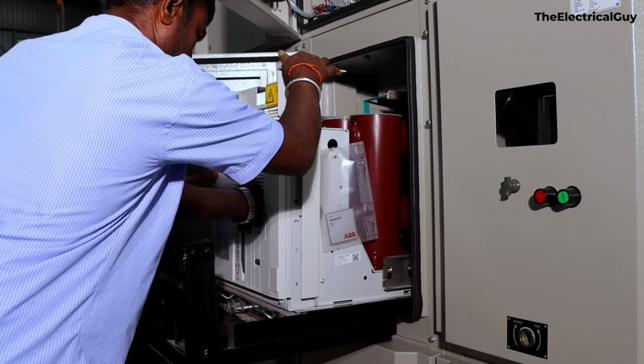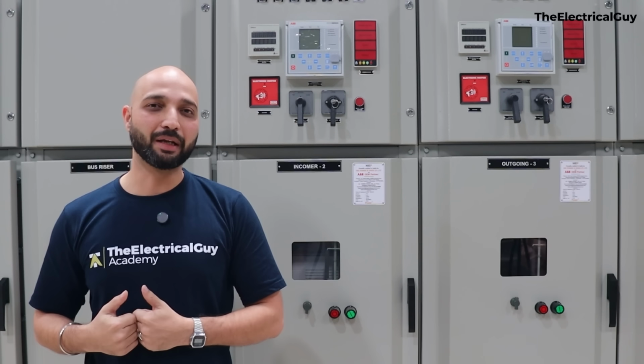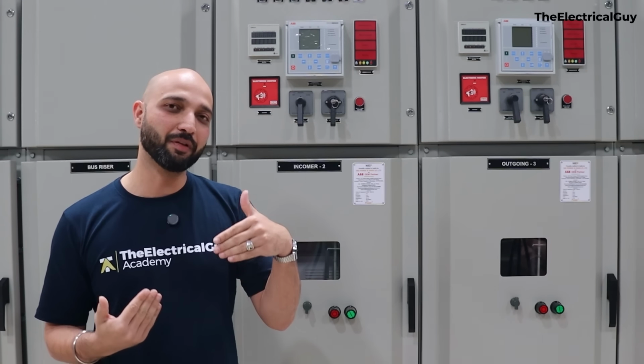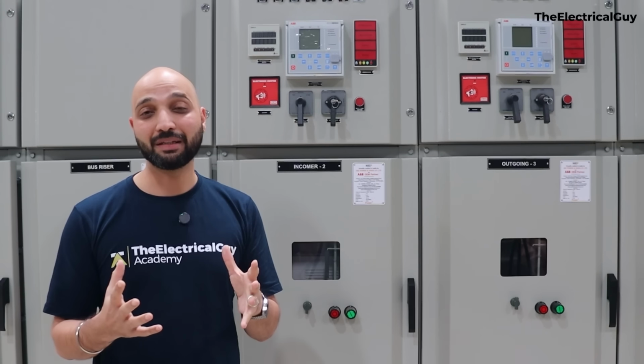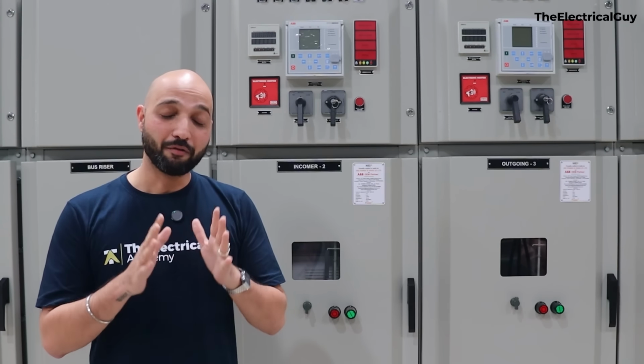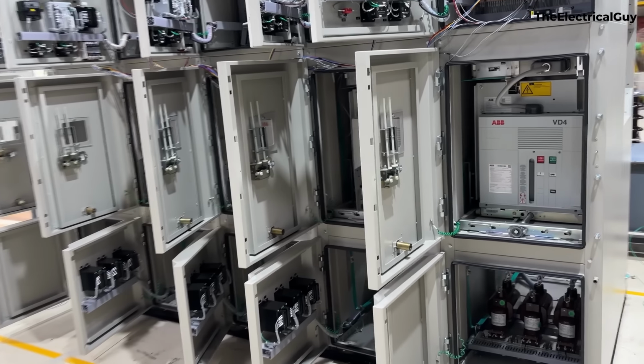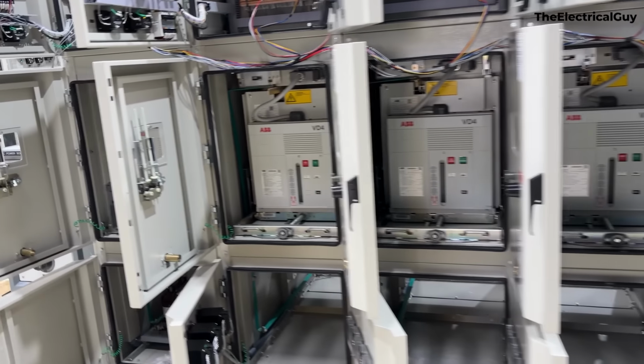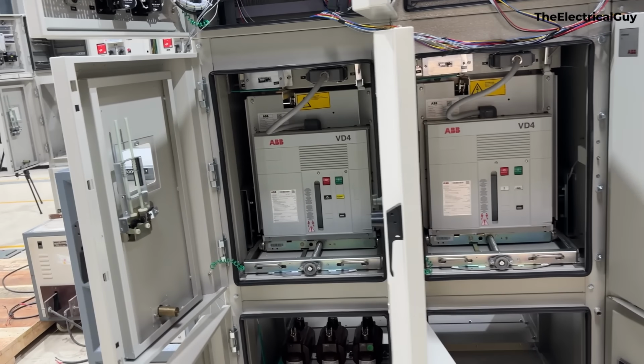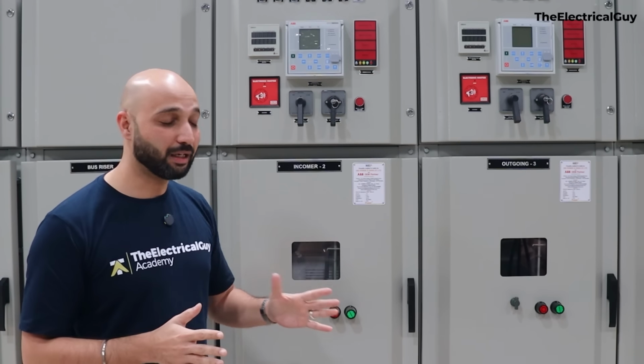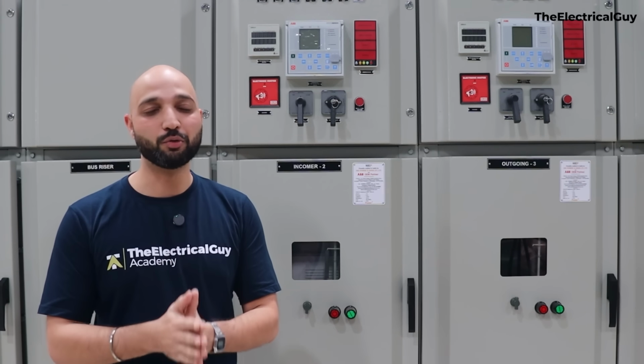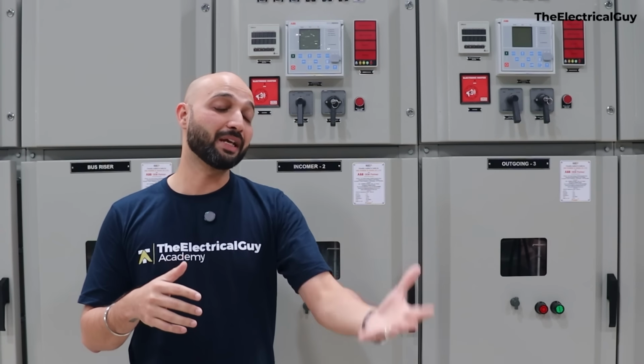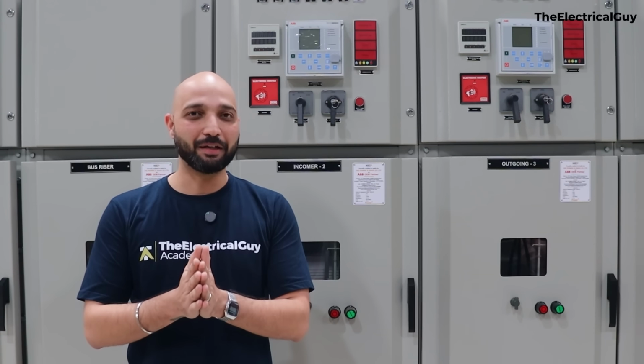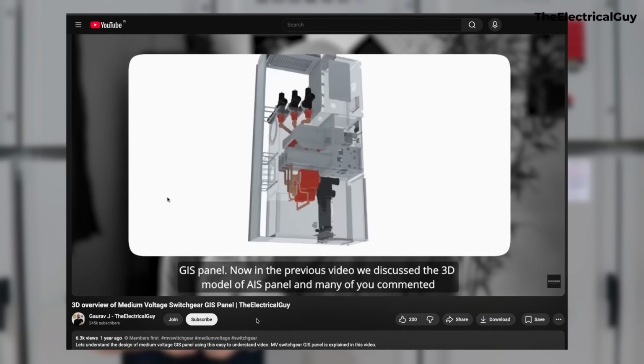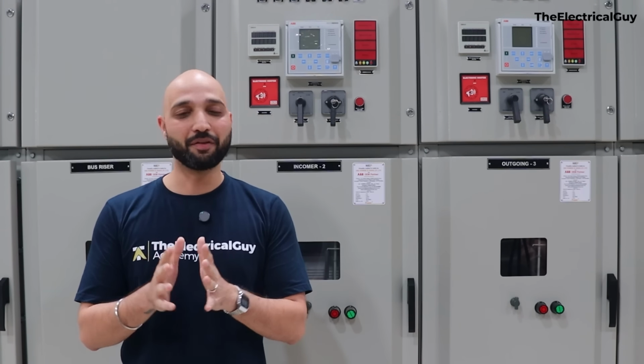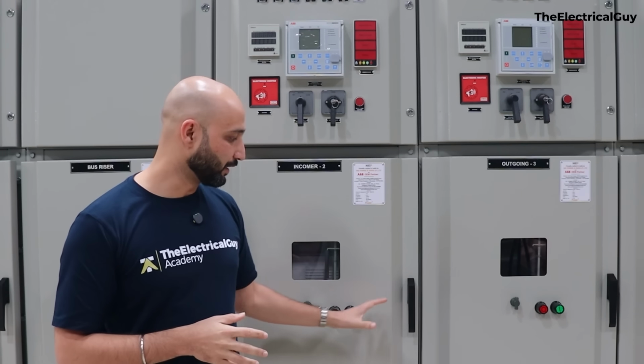Now the advantage with this, we already talked about. When you remove this breaker, we also get an isolating distance between the two live wires. That basically serves as an isolator. So when we use this withdrawable type circuit breaker, we don't need a dedicated disconnector or dedicated isolator supported by IEC standard. And that's why you will see in any of the panels that we have here, we are not using any isolator. But when we go to the gas insulated switchgear, there the breakers are not withdrawable. It's a fixed type, and there we definitely need the disconnectors. All right, so that is the circuit breaker.